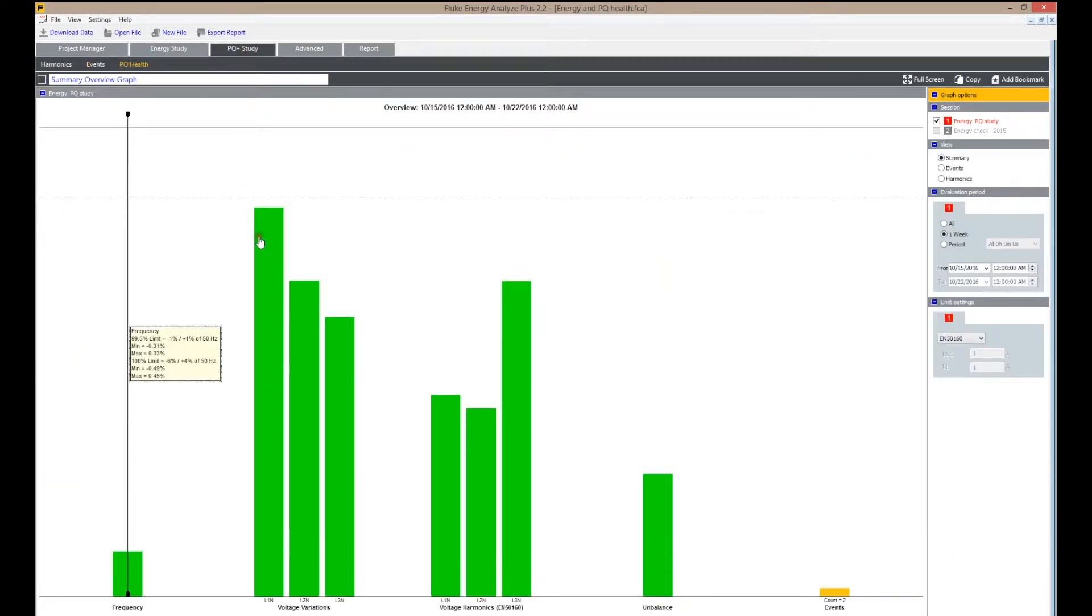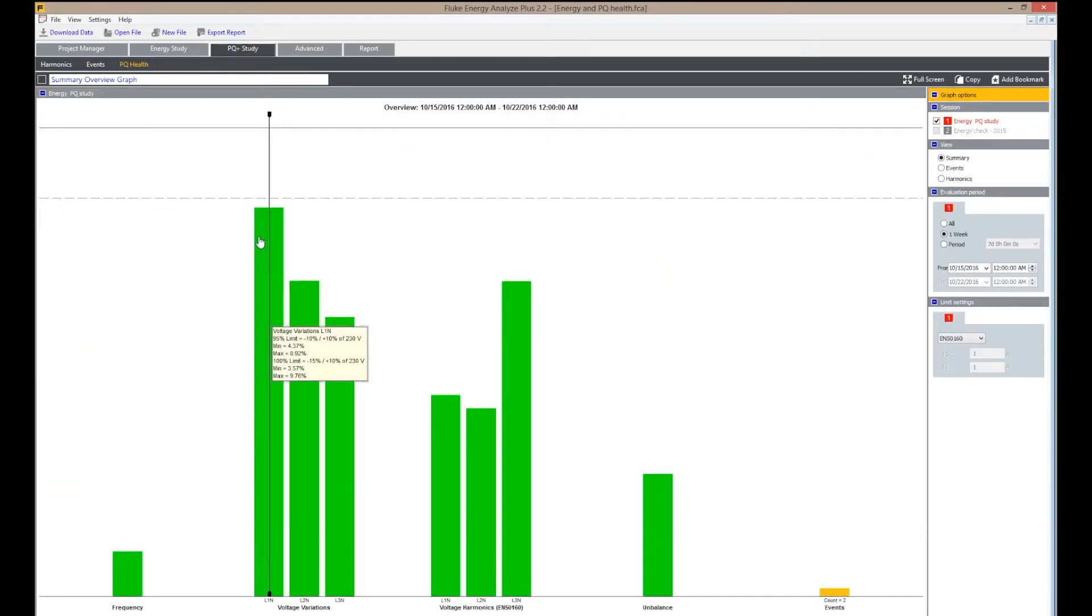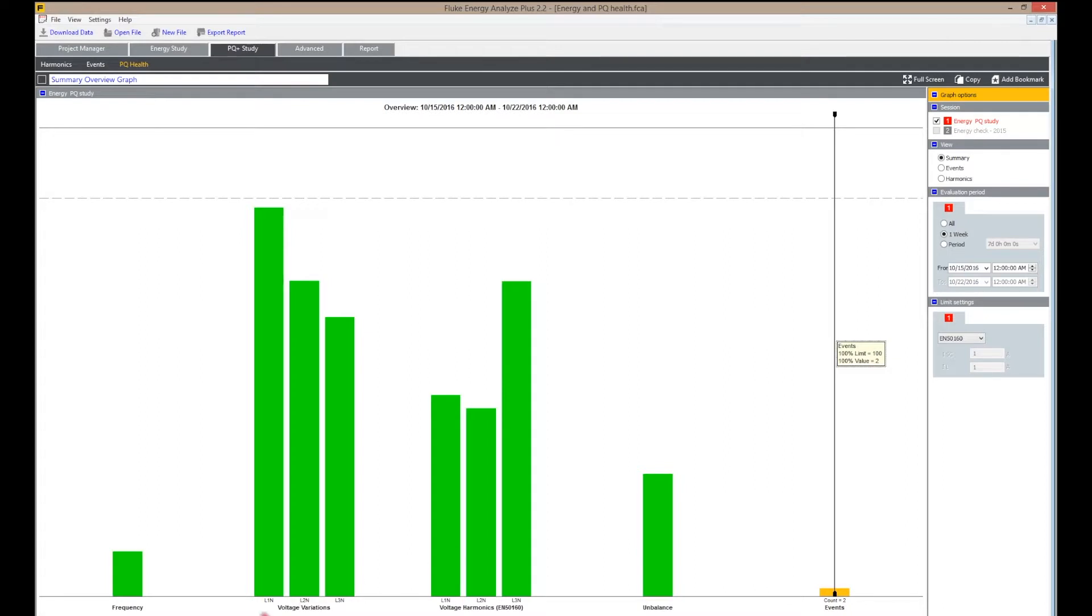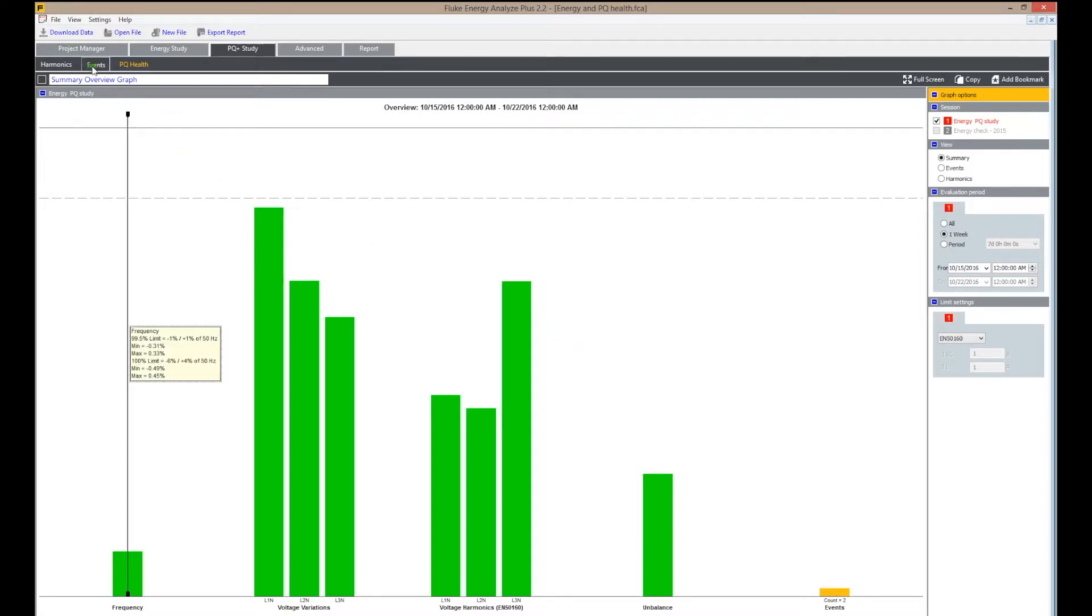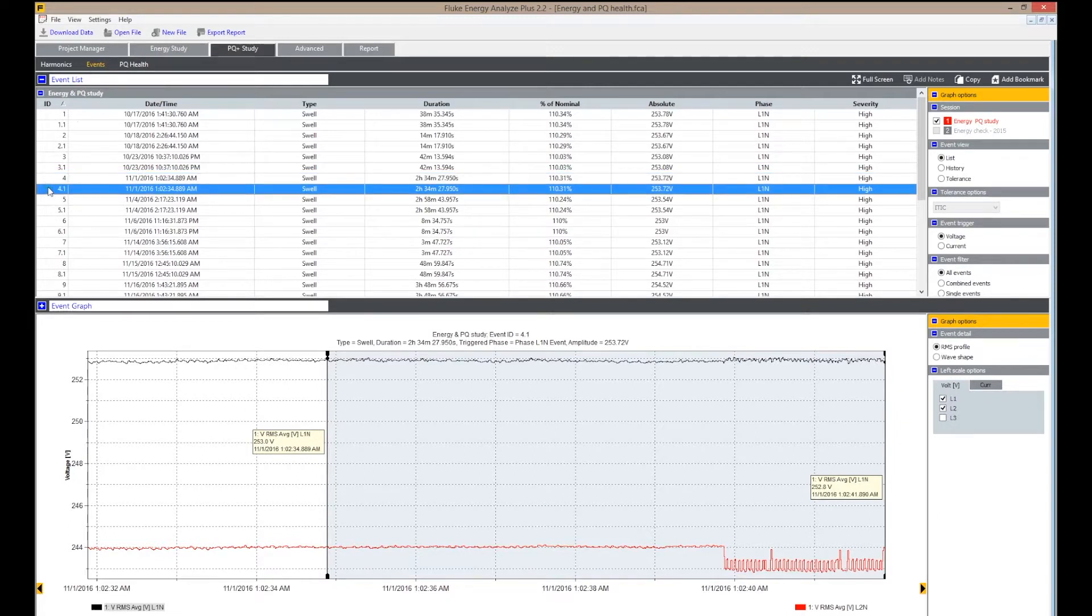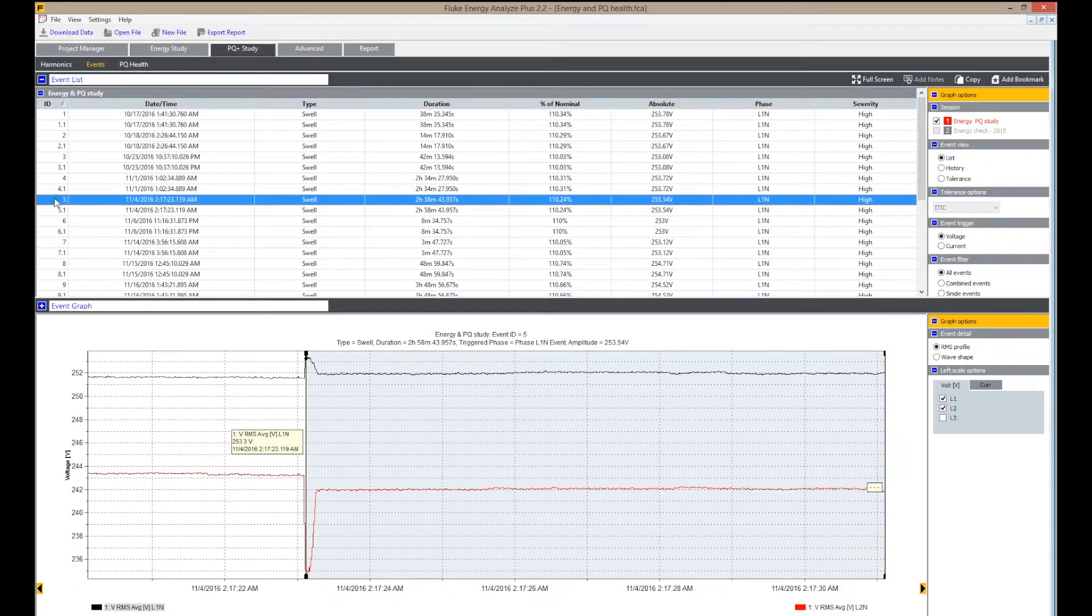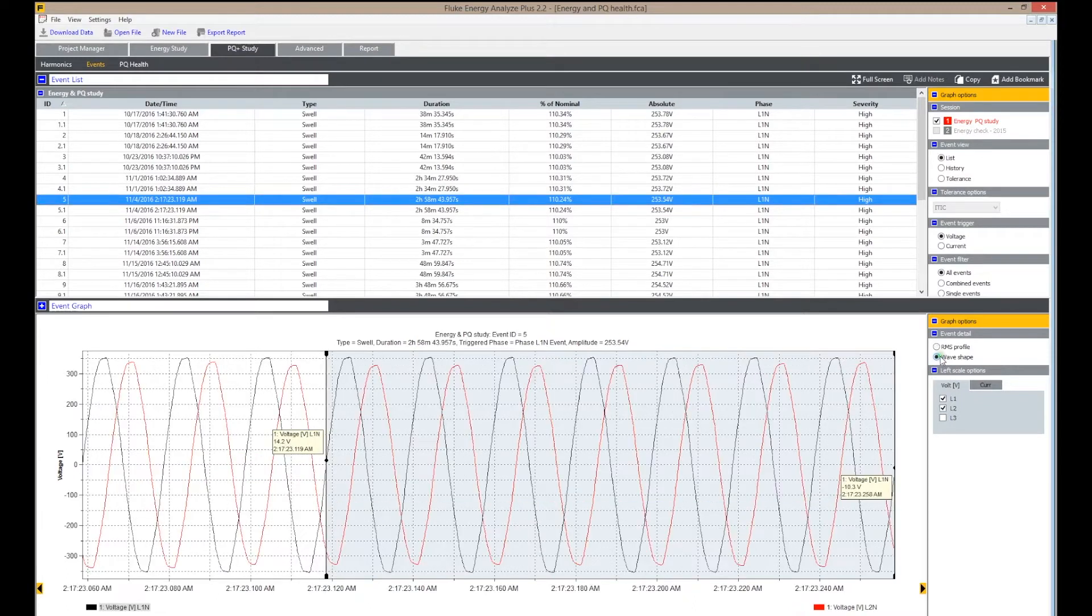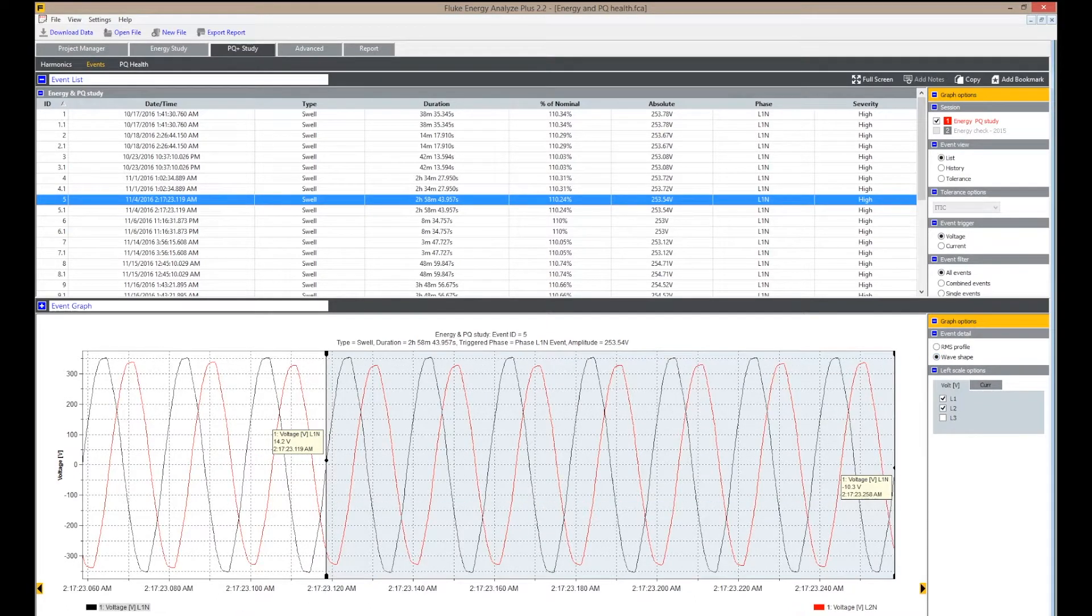For a power quality study, PQ Health gives a quick overview of voltage variations with exceedances of limits according to EN 50160. The events list shows the events that took place along with wave shape details. In addition, harmonic spectra are available.